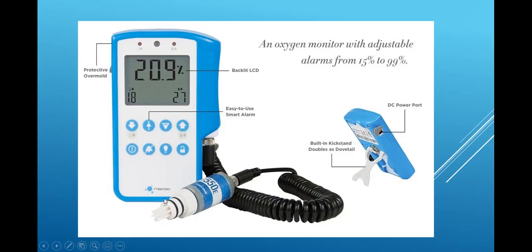When I stick this analyzer in the stream of a pure oxygen source, like a tank, it should read, no, not the pressure, this is percentages here. 21% in the room air. And if I stick it right into the flow of 100% oxygen, it should read what? 100%. And that's how you calibrate it, okay?